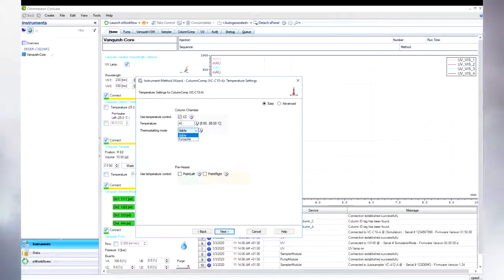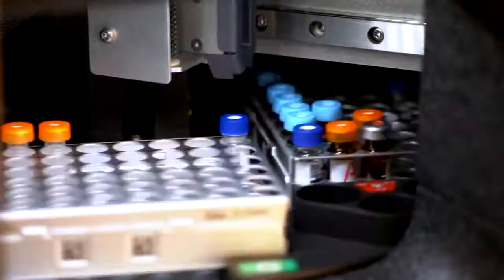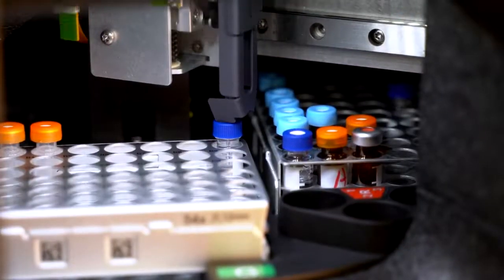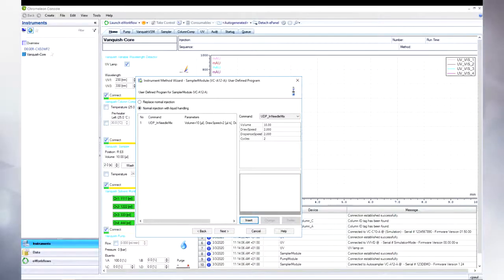Additionally, we have the only column compartment which can operate in two different thermostatic modes, which can be easily switched by a single mouse click. Last but not least, user-defined programs allow for in-needle dilution of strong solvent samples. This is a remedy for peak distortions due to solvent mismatches.